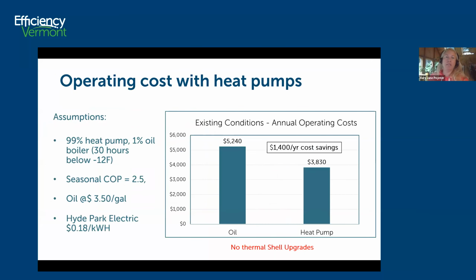So the first cost analysis I did was, let's just look at how much you would save if you did nothing to the building and you put in a bunch of one-to-one units, one for every zone in the building. So you've got a bunch of offices upstairs, some offices downstairs, and a stair column that goes from the basement up to the first floor. I used a seasonal coefficient of performance of 2.5. That is a little bit lower than a lot of the published data, but that is based on a couple of studies that people have done to try to calculate the real COP. And I think 2.5 is actually a little conservative. It was closer to 2.3. That's what we use in most of our calculations, a seasonal COP of 2.5.